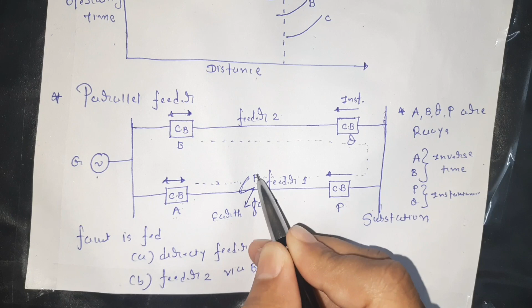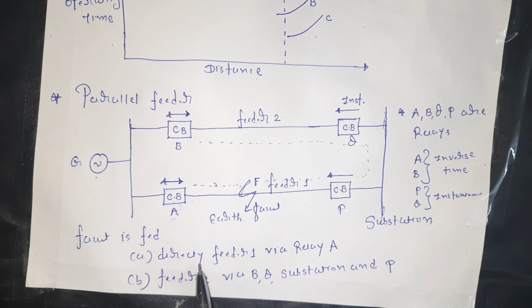Now let us discuss if there is an earth fault as shown here, F. The fault is fed via two paths. One is directly feeder 1 via relay A. And what is the second path? Second path is feeder 2 via relay B, Q, substation, P, and then the fault. So these are the two paths which I have mentioned.